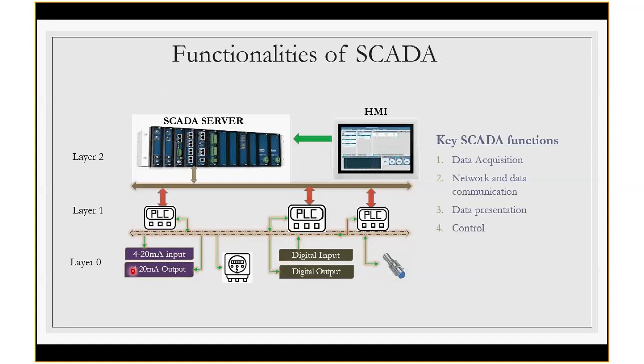Layer 0, what kind of sensors? 4 to 20 milliamp sensors like PT100, KTY10, and digital inputs and outputs. We can read some alarm inputs, activate some outputs, and use proximity sensors to measure speeds or detect rotations. Any physical analog or digital sensors connected to the PLC, this is layer 0.